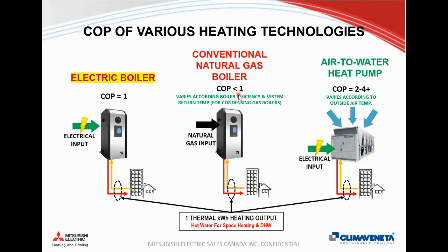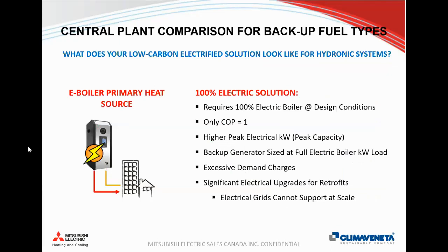If we have a condensing boiler and we actually have cold return temperatures coming back and we're actually condensing, we can get efficiencies as high as 95 to 98%. But if we look at all three of these devices, we have the same thermal output, just provided from different sources. So we're going to compare those. So if you did want to just take a natural gas boiler and change it out to an electric boiler, we could certainly do that.